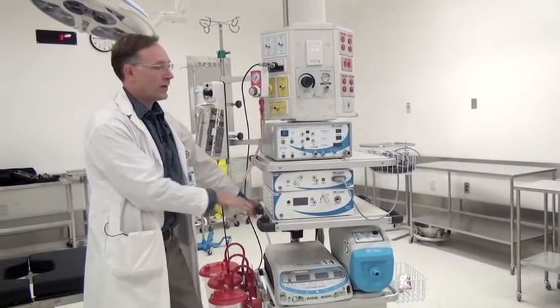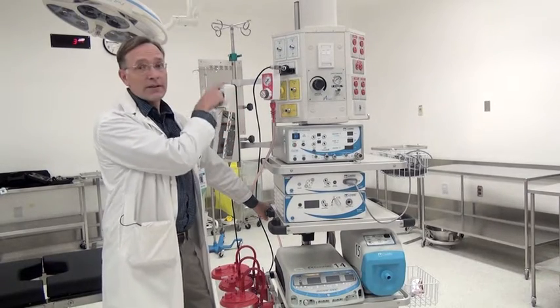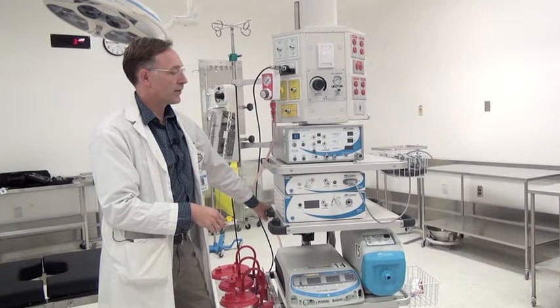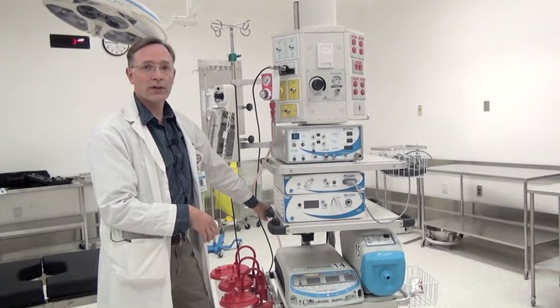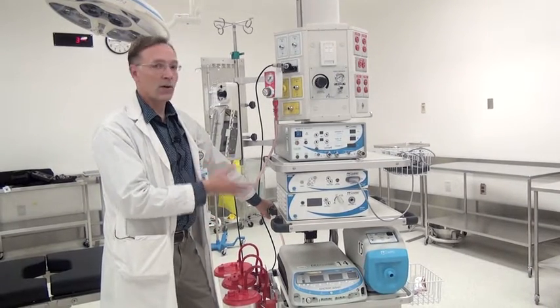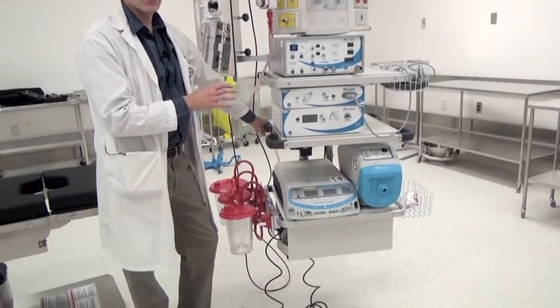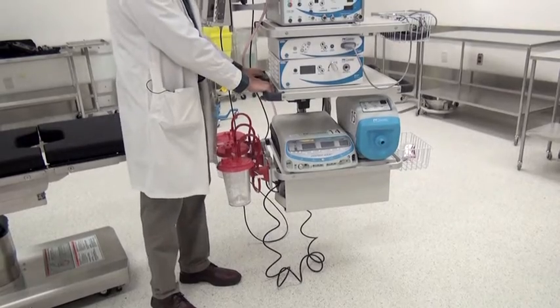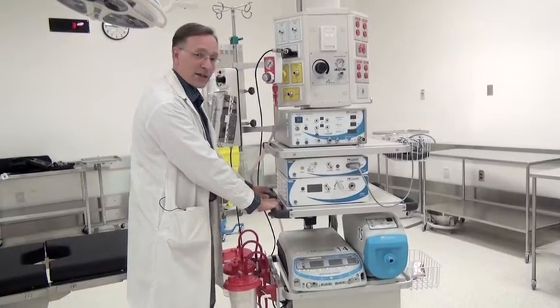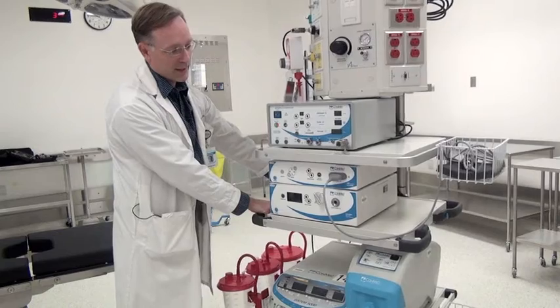Previously the equipment would be on separate carts. The electrical supply to this unit would come not from the ceiling but through wires that would travel across the floor, and there was obviously some potential risk of tripping and falling over those. This new unit allows us to get all of that electrical support off of the floor, and we can move this unit independently anywhere in the room with a system of hydraulics within the boom. If you listen carefully you can actually hear the hydraulics firing as I press these buttons, and then we can move this boom freely throughout our operating room wherever it's needed.